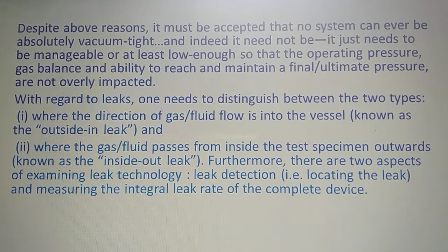Moreover, there are two aspects of examining the leak technology and leak detection, that is locating the leak and measuring the integral leak rate of the complete device. So this leak detection is a very critical process. Let's move ahead to leak detection, and there are basically four different types of tests which help to detect the leak. The first is the bubble test, second is the pump down test, third one is the pressure rise test, and fourth one is the pressure drop test. There is one more test called helium leak detection. We are going to study these in the next few slides.